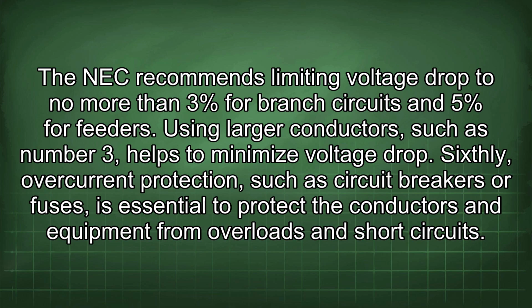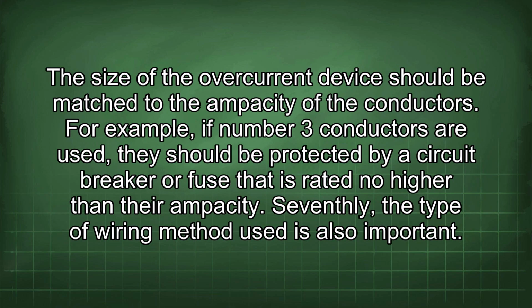Using larger conductors, such as number 3, helps to minimize voltage drop. Sixthly, overcurrent protection, such as circuit breakers or fuses, is essential to protect the conductors and equipment from overloads and short circuits. The size of the overcurrent device should be matched to the ampacity of the conductors. For example, if number 3 conductors are used, they should be protected by a circuit breaker or fuse that is rated no higher than their ampacity.